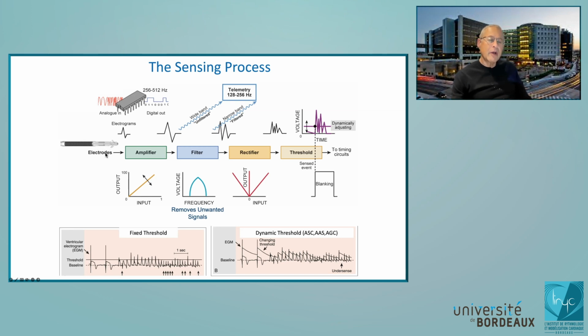When the signal comes out of the pacing lead, the first thing that happens is that it's amplified. And this amplified signal is what Abbott displays as the ventricular bipolar signal. After the signal is amplified, it's filtered. The purpose of filtering, as a good EP tech like Hamad will tell you, is to remove unwanted signals. For example, remove higher frequency signals such as electromagnetic interference or lower frequency signals like T waves.